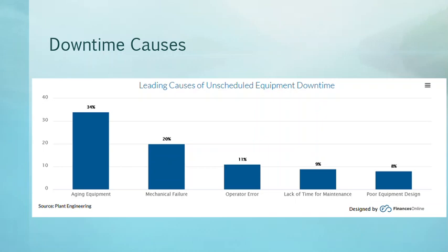Poor design is another place that can easily be corrected. For instance, we encountered a water-cooled drive system where the pump starter had failed within the first year. After reviewing that starter, it was sized right at the top of its rating. We replaced that starter with just one size larger, and that eliminated the issue of the starter failing.